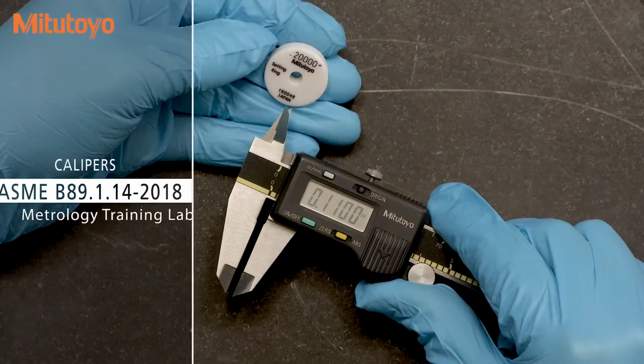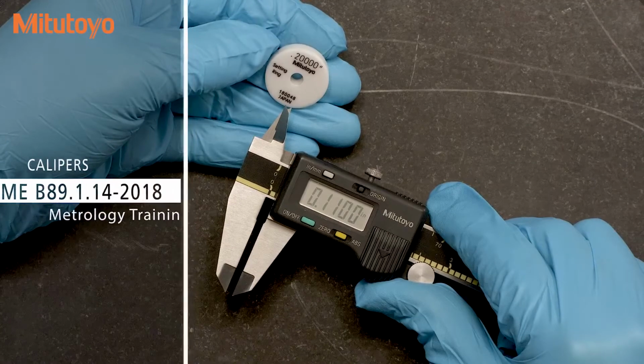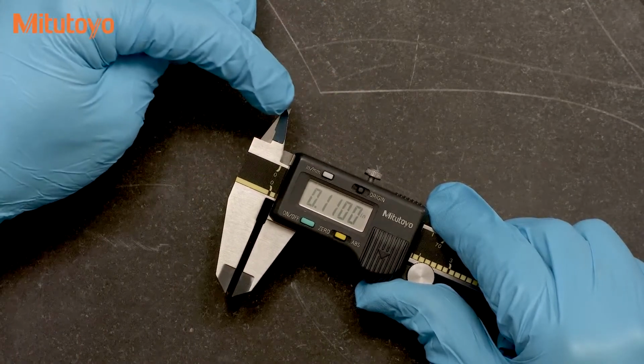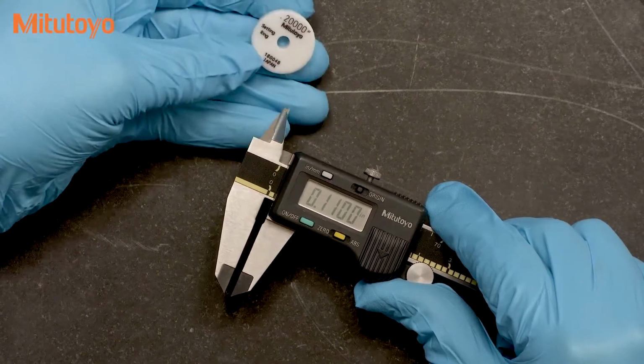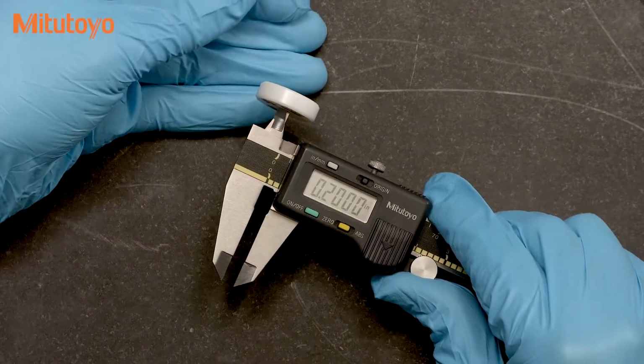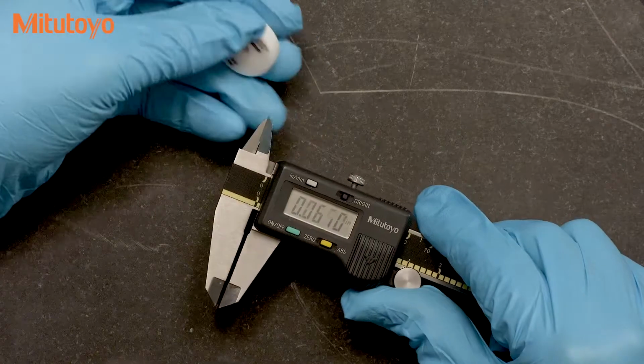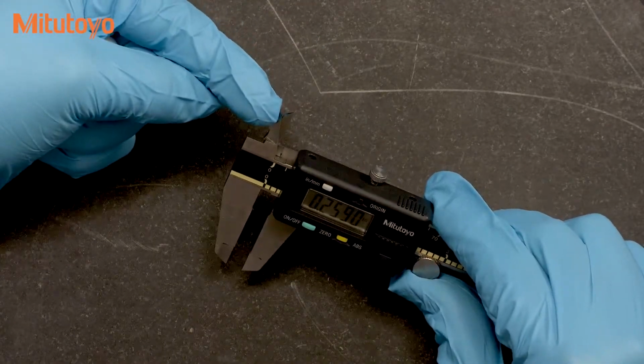For calipers, the ASME B89.1.14 standard discusses the need to check the internal measuring jaws with a small ring gauge around 0.2 inches in diameter. This test is specifically designed to test for the additional error that can occur due to the crossed knife edge measuring faces. Lastly, on surface plates, the ASME B89.3.7 standard discusses the importance of the two different flatness specifications for surface plates. One being a local flatness, often called the repeat reading, and the other being the overall flatness, which covers a much larger area of the entire surface plate. A proper calibration needs to address both flatness specifications.